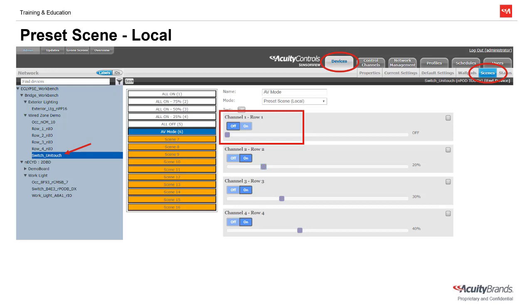As you can see, we've told Row 1 to be off, and Rows 2, 3, and 4 to be at 20, 30, and 40%. Once named and saved, when this AV mode button is pressed, no matter what the light levels are currently at, they will all immediately change to these prescribed levels. They will remain here until another button is pressed or the room is unoccupied. As a reminder, this Local Preset Scene is stored on this device and cannot be run on a time schedule or from other devices outside this control zone or room.